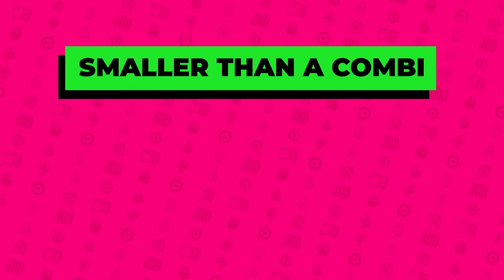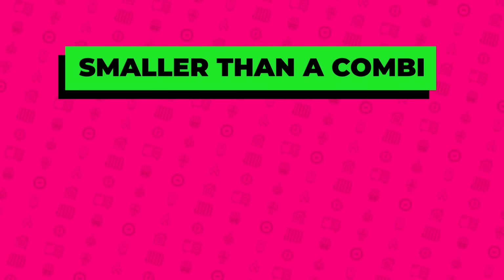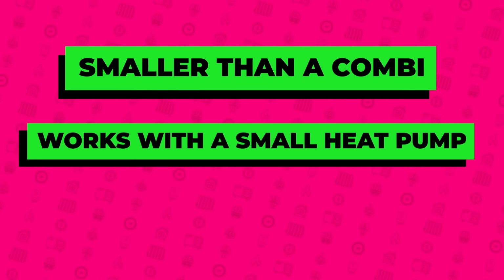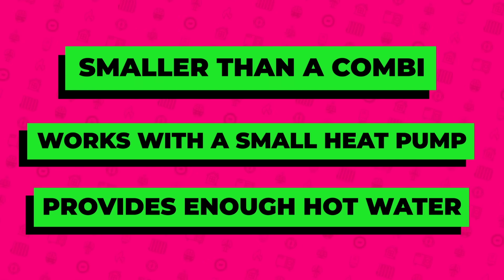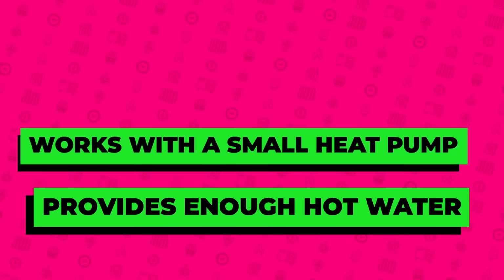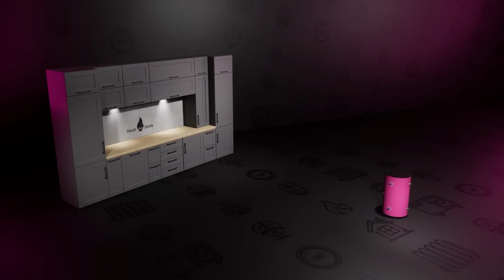So I'm attempting to create something smaller than the smallest combi boiler that can be powered by a small domestic heat pump and provide enough hot water for showers and baths for these 80% of homes. And if we can achieve this, we will finally fully unlock heat pumps for the 80% of homes that currently can't have one.